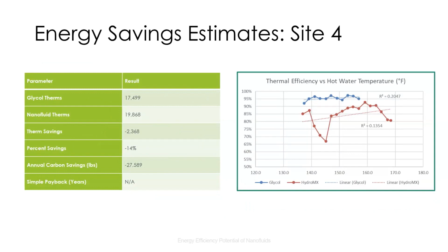Our analysis for this site involved normalizing the results only by supply water temperature. On the graph at the right, the baseline line is blue, and that's higher than the nanofluid line in red. So it kind of shows that there's negative energy savings here. In terms of the total load calculated in the nanofluid, we applied those loads to the average efficiency of 96% in the baseline. As you can see, it's a relatively flat performance there based on hot water temperature, and that determined the energy savings, which, as you can see, are negative in this case.